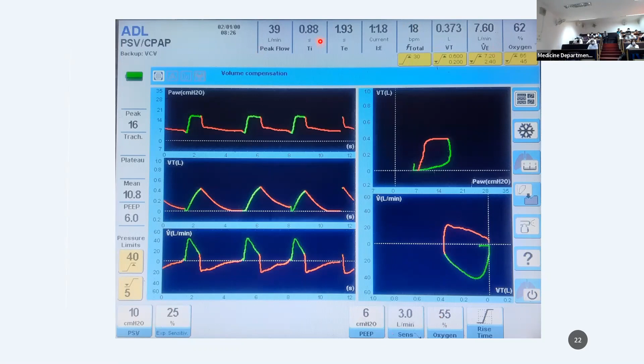Flow cycle means that, for example, here, inspiration begins and the flow begins. Then the flow reaches a peak flow. This is the pressure scalar, this is the volume scalar, this is the flow scalar. So it reaches a particular flow. When the flow reaches 25% of this peak flow, then it cycles into expiration. So this is the meaning of expiratory sensitivity. If I increase the expiratory sensitivity to, for example, 30%, it will cycle earlier. If I change the expiratory sensitivity to, for example, 5%, then 5% will come somewhat here, so it will cycle late. Okay. So flow cycling is important. And again, the set parameters are very different from the parameters being delivered to the patient.